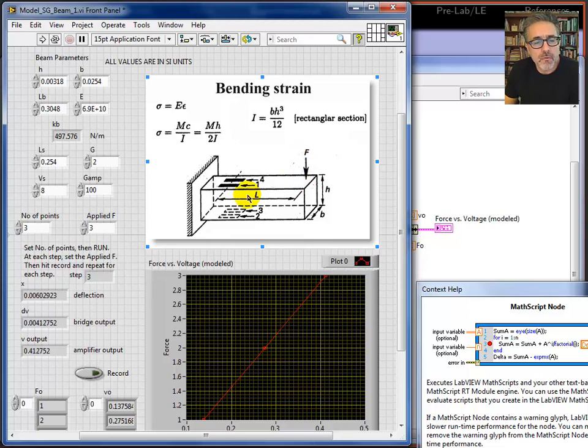We've got a tip force, four gauges that are presumed wired in a full bridge. There's two on top, two on the bottom face. Relevant equations here. And all the parameters in SI units can be put on the front panel.